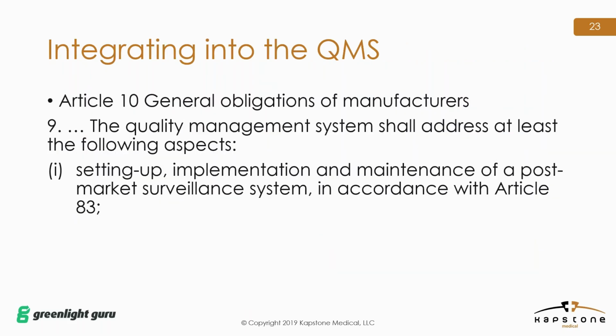All right, so now that I've gone over what's actually required straight from the EU MDR regulations themselves, I'm going to talk a little bit about how you can integrate the post-market surveillance requirements into your current quality management system. So Article 10 discusses the general obligations of a manufacturer, and then specific to Section 9I, it says the quality management system shall address at least the following aspects: setting up, implementation, and maintenance of the post-market surveillance system in accordance with Article 83. Just showing you that there's a requirement stated in there that you do need to incorporate this into your quality management system.